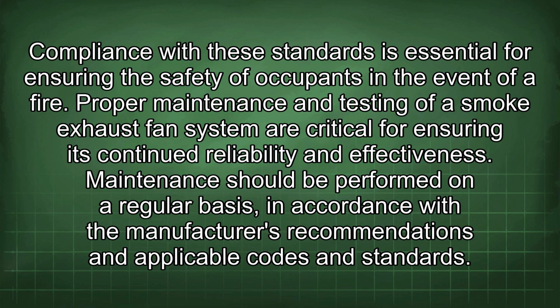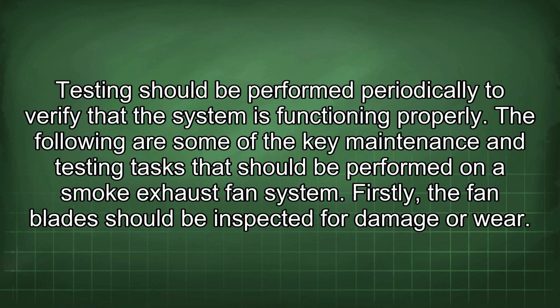Proper maintenance and testing of a smoke exhaust fan system are critical for ensuring its continued reliability and effectiveness. Maintenance should be performed on a regular basis in accordance with the manufacturer's recommendations and applicable codes and standards. Testing should be performed periodically to verify that the system is functioning properly. The following are some of the key maintenance and testing tasks that should be performed on a smoke exhaust fan system. Firstly, the fan blades should be inspected for damage or wear.